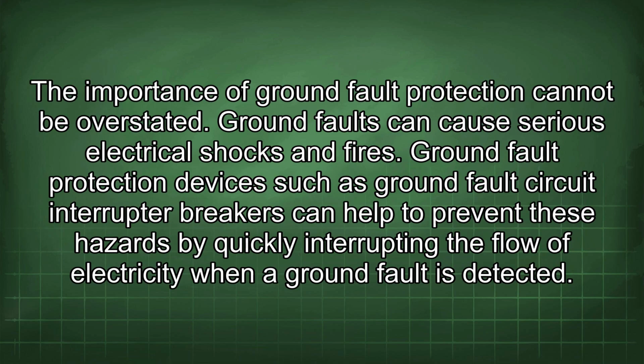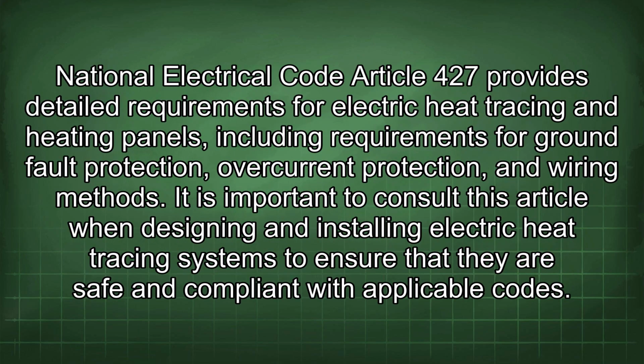The importance of ground fault protection cannot be overstated. Ground faults can cause serious electrical shocks and fires. Ground fault protection devices such as ground fault circuit interrupter breakers can help to prevent these hazards by quickly interrupting the flow of electricity when a ground fault is detected. National Electrical Code Article 427 provides detailed requirements for electric heat tracing and heating panels, including requirements for ground fault protection, overcurrent protection, and wiring methods. It is important to consult this article when designing and installing electric heat tracing systems to ensure that they are safe and compliant with applicable codes.